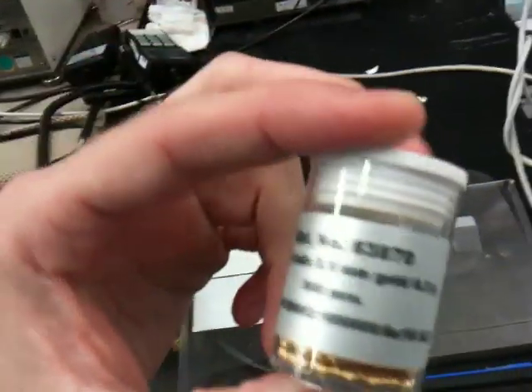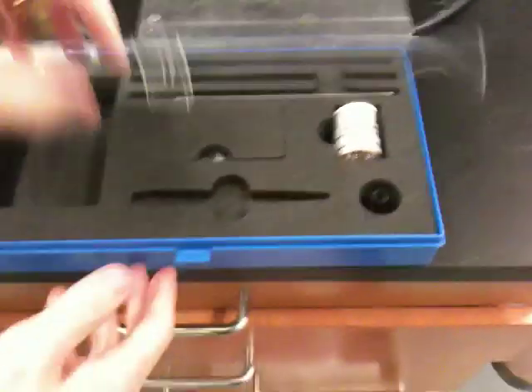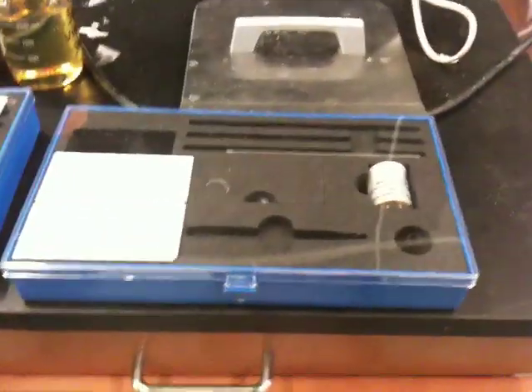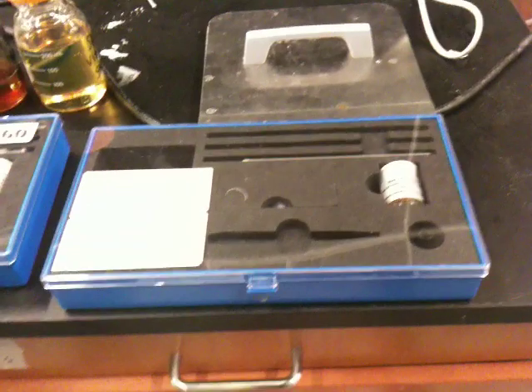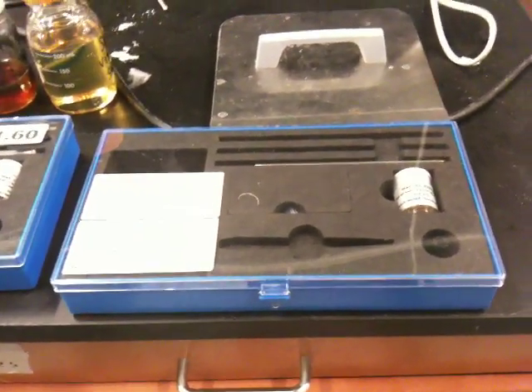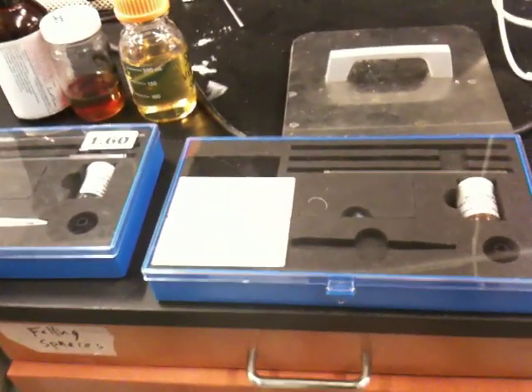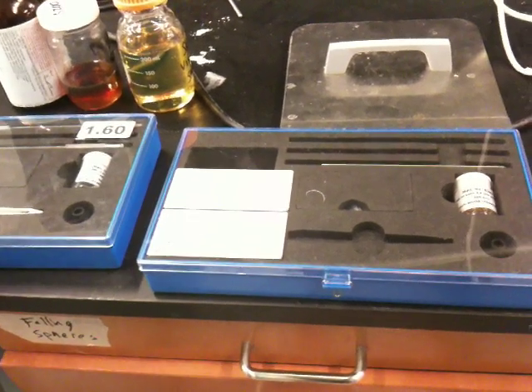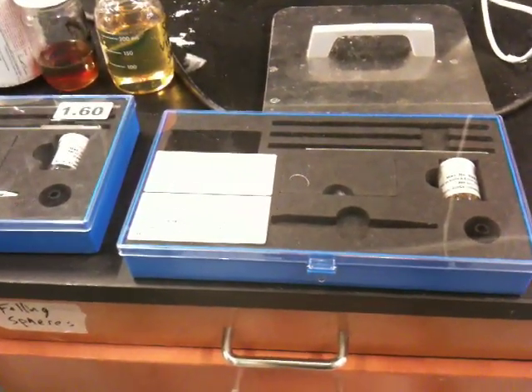Both of these use the gold beads. Right here. You just need one of them. If you ever lose the gold bead, you have to recalibrate the machine. Or if you ever have to use a different capillary, you have to recalibrate it for that capillary and that bead.